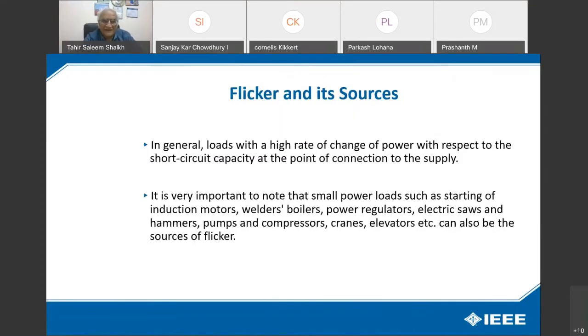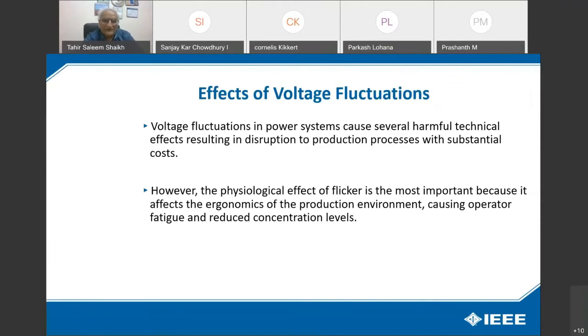In general, loads with a higher rate of change of power with respect to the short circuit capacity at the point of connection to the supply. It is very important to note that small power loads such as starting of induction motors, welders, boilers, power regulators, electrical saws and hammers, pumps and compressor cranes can also be the source of flicker whenever the transient occurs. Voltage fluctuation in power systems causes several harmful technical effects, resulting in disruption to production processes with substantial cost. However, the physiological effect of flicker is the most important because it affects the ergonomics of the production environment, causing operator fatigue and reduced concentration levels.